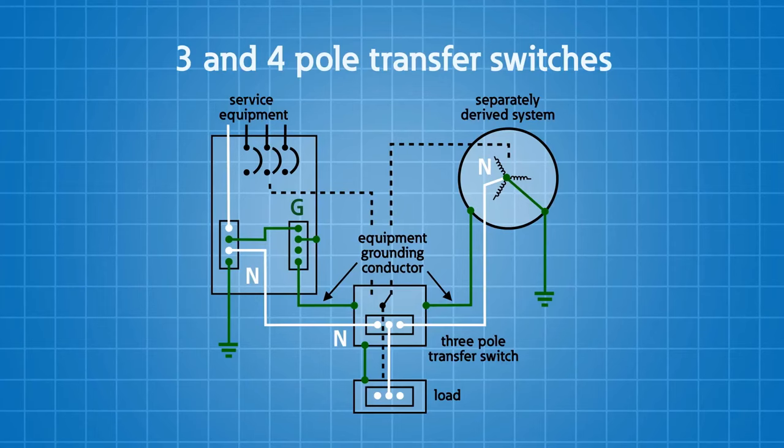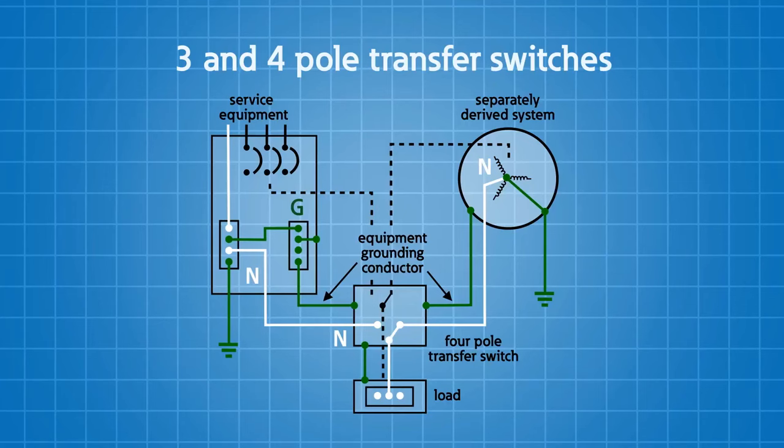A separately derived system implies that you would have a grounding electrode system and you would bond the neutral, the grounded conductor, in the generator with that system. If you have a separately derived system, the implication is that the transfer switch must switch the neutral with a four-pole transfer switch.